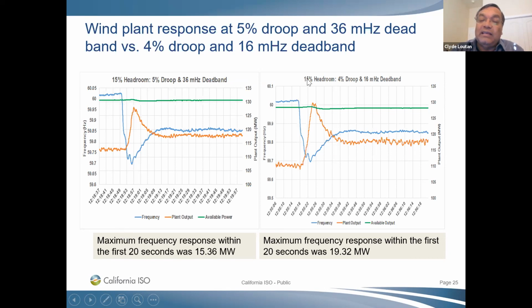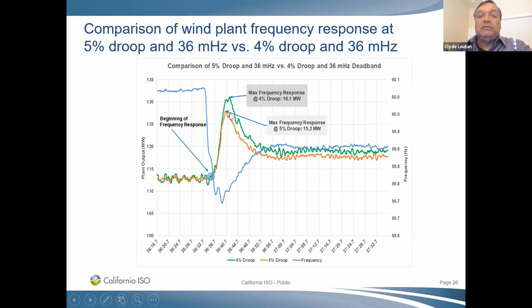While by just dialing a change, which is just a software change, from going from a 5% to a 4% droop, and changing that deadband from 36 millihertz to 16 millihertz, you can see you can get roughly 4 megawatts more response by doing nothing other than changing the droop and the frequency bandwidth. So this was very interesting also. And then looking at both responses here, at 36 millihertz, so a 5% droop and a 4% droop, you can clearly see that you get better response with a 4% droop as opposed to a 5% droop, even though the deadband was the same, 36 millihertz.